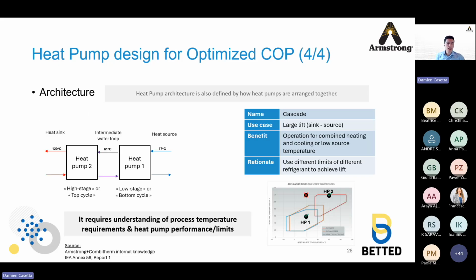Another technique is arranging heat pumps together in the right way. In this example, we are showing you the cascade, which is enabling the use of a large lift, so a large temperature difference between the cool and the hot side of the heat pump. And it's basically using different limits of different refrigerants to achieve that lift. Said differently, if you had a single heat pump with a single refrigerant, thermodynamically, technologically, you couldn't achieve that lift.